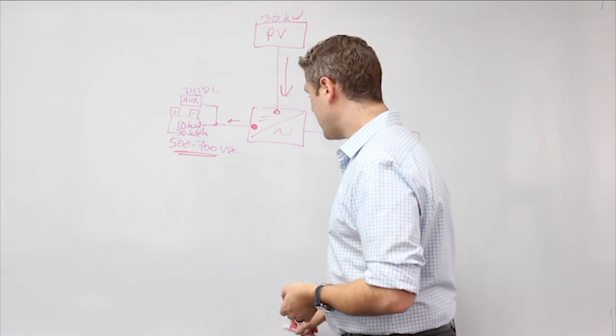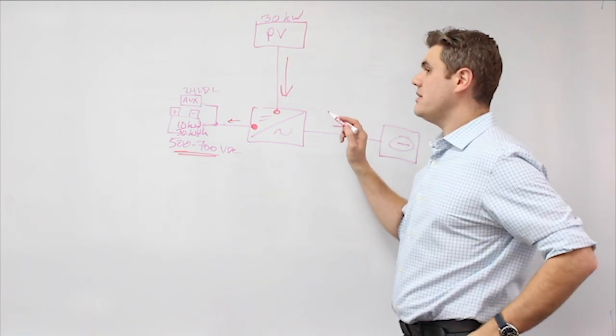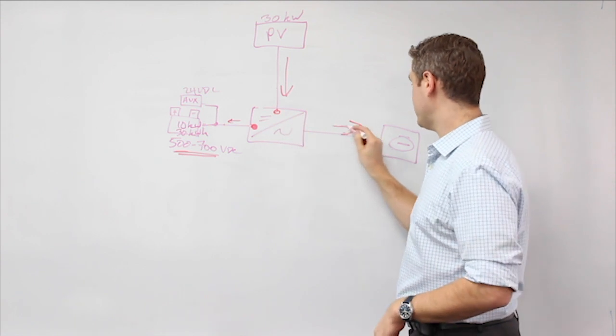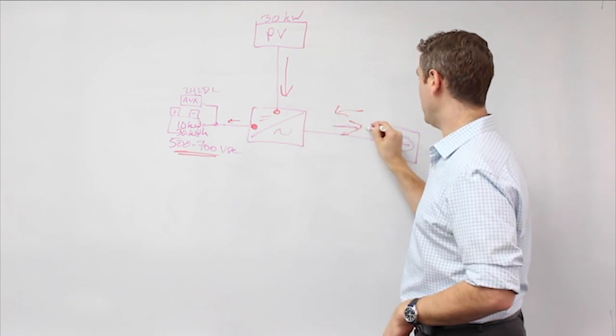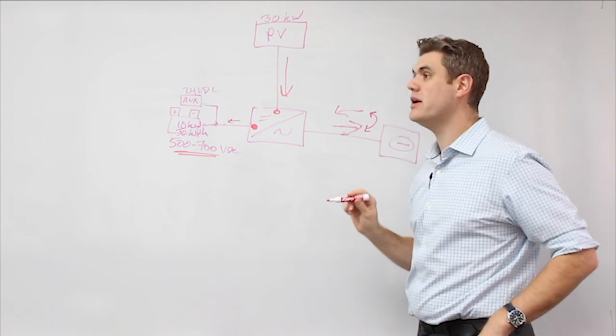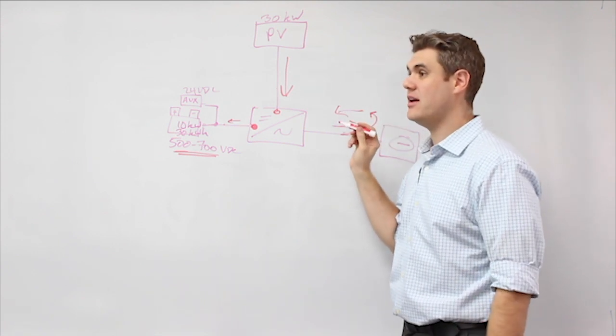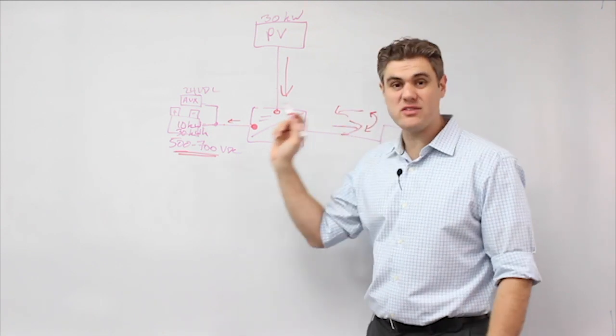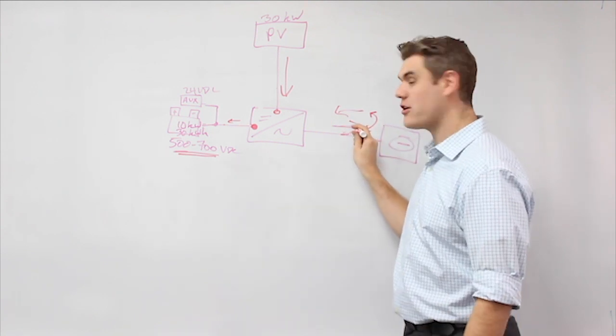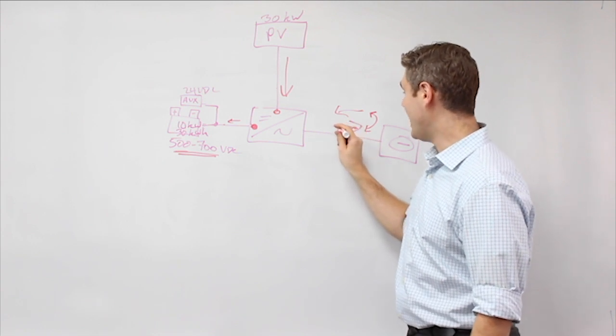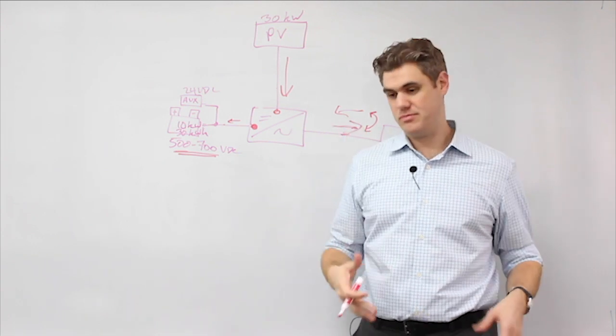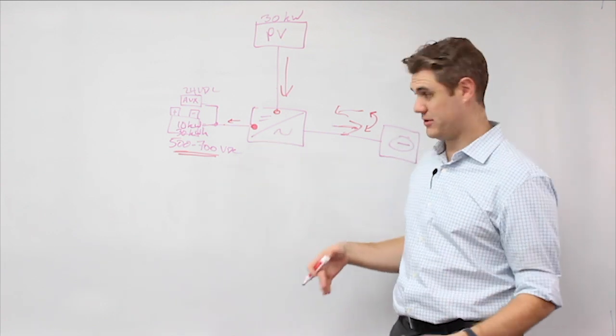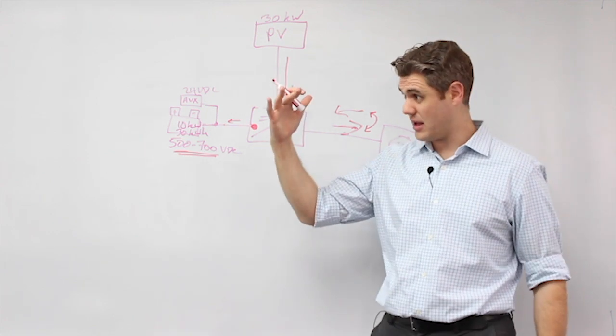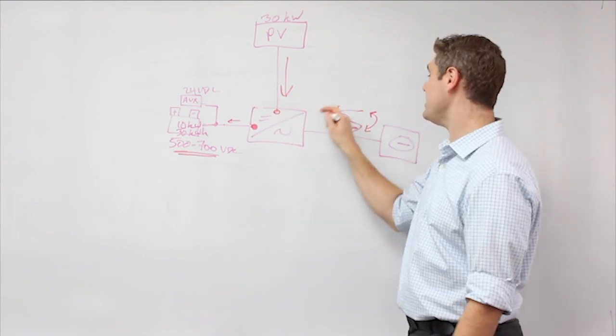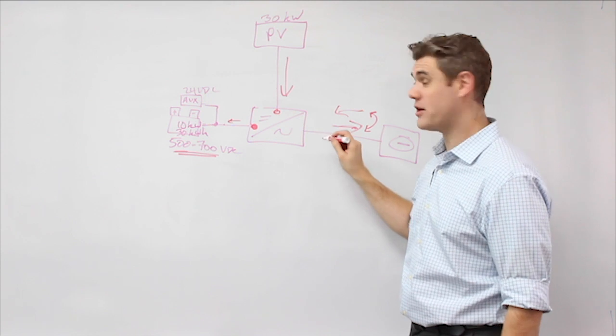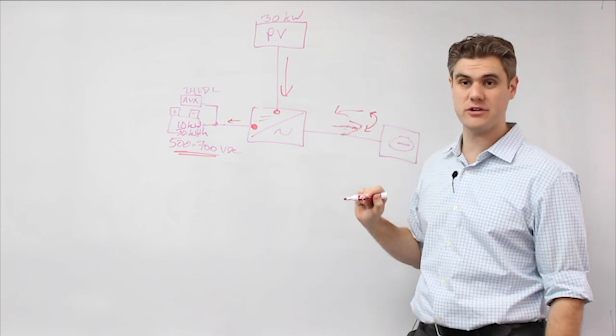one of the tests is they want to make sure that when this inverter switches from export to import, when it flips between the two, that just before it does that, it'll be able to sense that this arrow is getting smaller and smaller and is about to flip. So they put this inverter on a bench or in the field, and they witness test: as the solar is coming down, can it actually see and measure and monitor and report on the power flow on this side of the inverter?